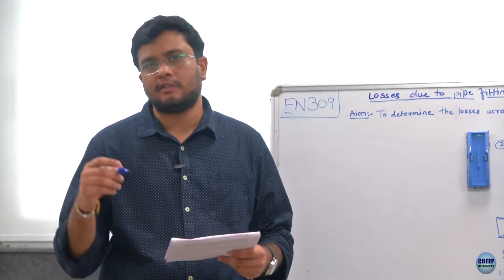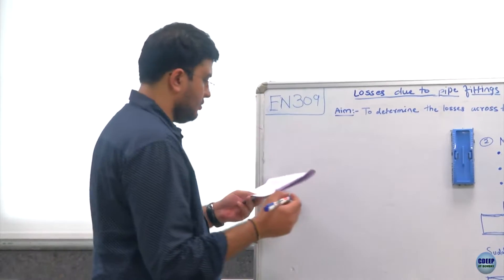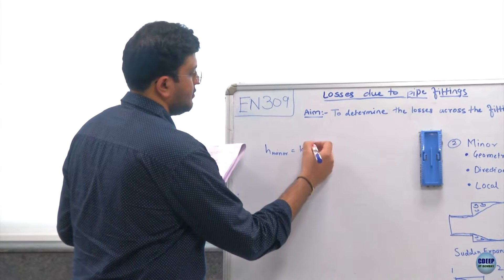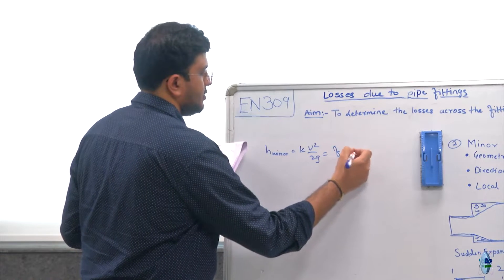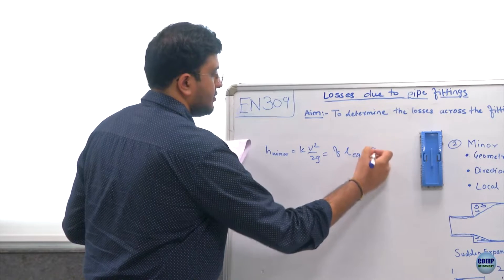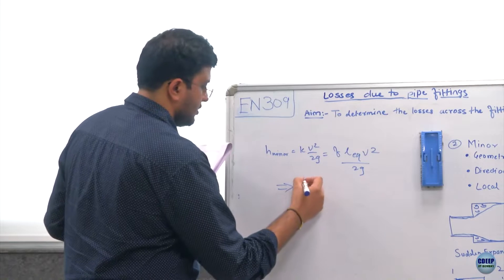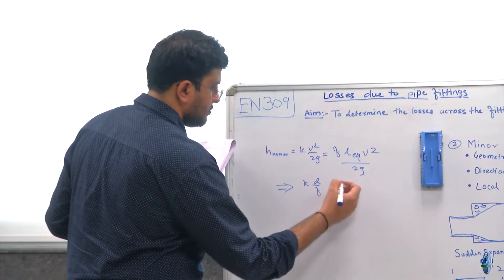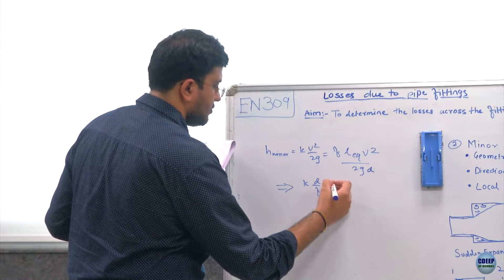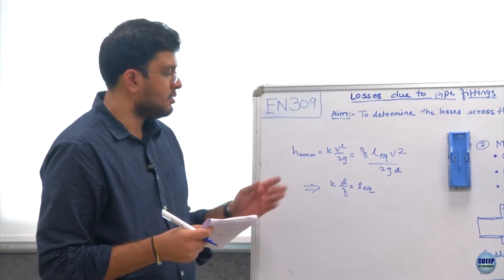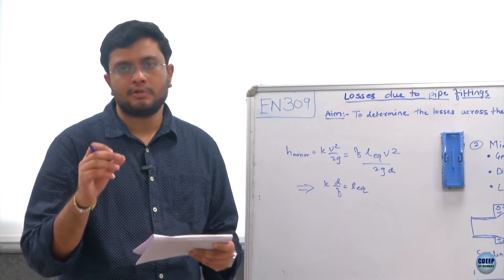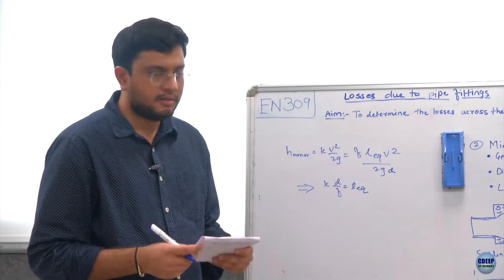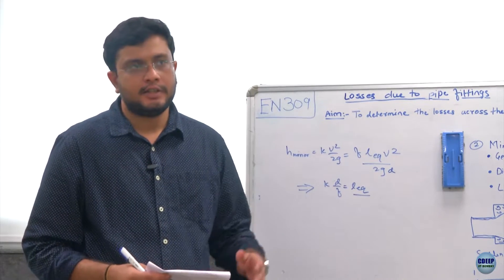Minor losses are also expressed in terms of equivalent length of a straight pipe. The equation is: H_minor = K · V²/(2g) = f · L_equivalent · V²/(2g·D), which gives L_equivalent = K·D/f. This equivalent length represents the length of straight pipe that would produce the same head loss as the fitting. We will also calculate L_equivalent for each fitting in today's experiment.